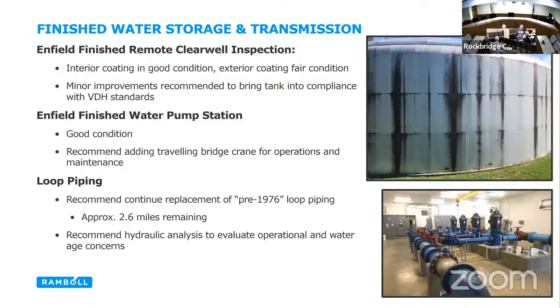As part of the facilities assessment, we brought the rover out to the remote clear well to complete an interior inspection, similar to what we did at the water plant's clear well. We also completed an exterior inspection. What we found is similar to the water plant's equipment: for its age it's not too bad, but it hasn't been maintained or rehabilitated. So there's a list of improvements needed on both the exterior and interior to maintain the longevity of that tank.